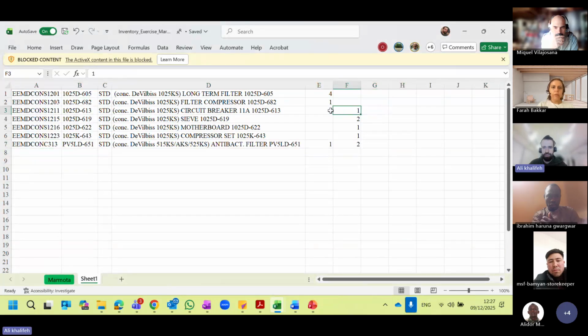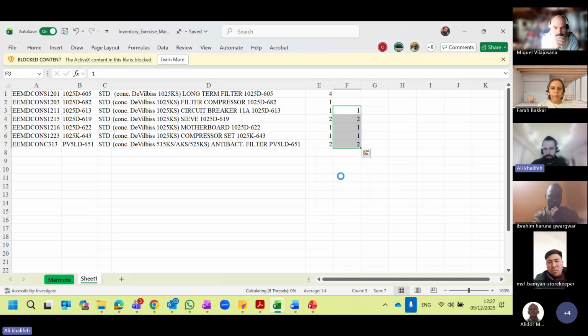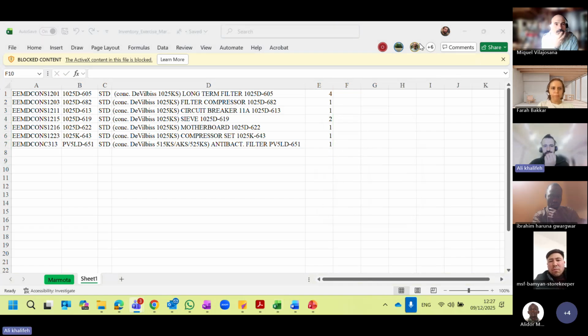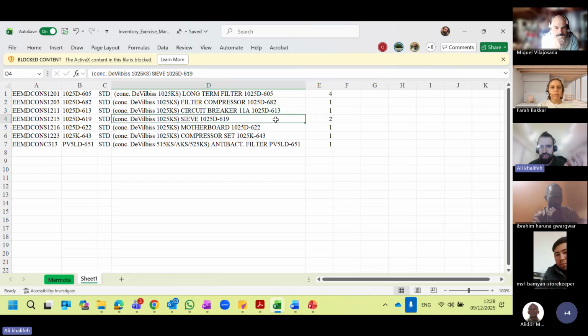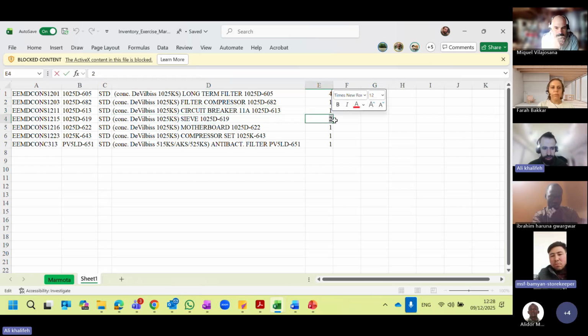And the quantity is 4, 1, 2, 1, 1. Antibacterial filter. The idea, it's clear, guys, how to calculate, how to bring the information. So long-term filter, we need 4. Filter for compressor, we need 1 to be changed yearly. Circuit breaker, 1 as spare parts backup. Sieve, 2 as we have 1 concentrator as backup.